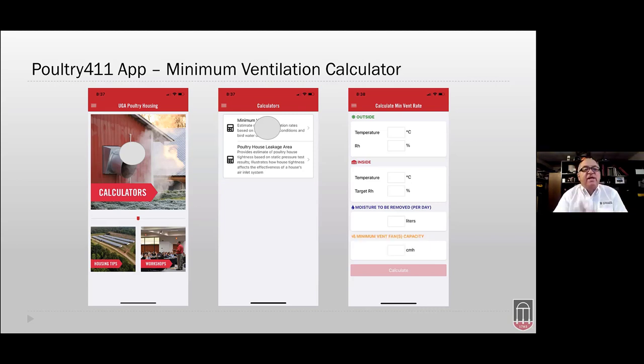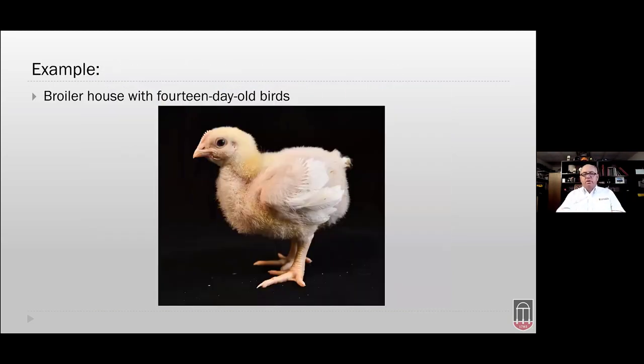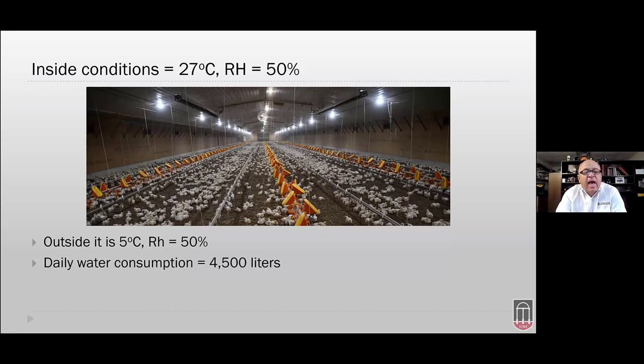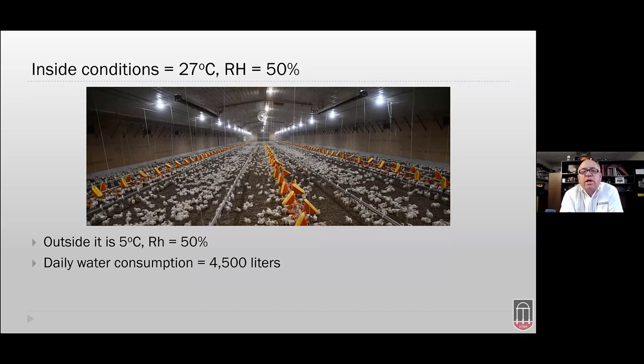You input the fans you want to use for minimum ventilation, and the app determines how long they need to run to remove a given amount of water under the conditions you input. For example: a broiler house with 14-day-old birds, inside conditions 27°C at 50% humidity, outside 5°C at 50% humidity, and daily water consumption of 4,500 liters. I don't care how many birds are in the house — all I need to know is how much water is going in to balance my ventilation.